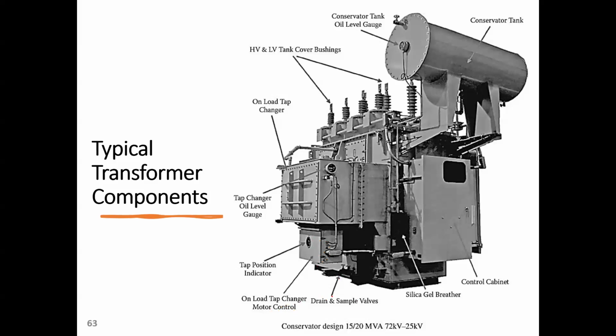Here you can find this arrow refers to drain and sample valves. Drain and sample valves for what? Drain for the oil, so you can get some oil samples from the transformer. The transformer here is going to be filled with oil. And the oil again, why do we have oil inside the transformer itself? It's mainly for cooling. But again, if you have, due to any reason, some faults inside, this is going to damp the sparks and avoid sparks inside the transformer parts. So this is also another function of the oil inside the transformer.